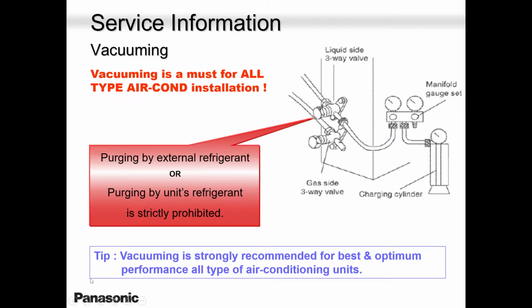Again, we spoke about vacuuming. Depending on your day, if you have high humidity, guys, please vacuum it longer. Okay, please, instead of using half an hour to get down to 300 microns or below 500 microns, go longer. Get rid of all that moisture, especially on a humid day.